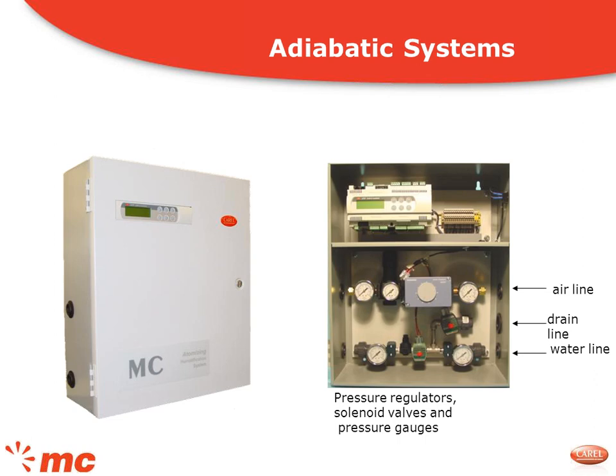Some of the single zone systems that you see are some of the zone controllers that can also be used, like this one that you see here. Just to see inside the box, you've got the direct air line where pressurized air would come in, and then you have your water line. You would supply both the air line and the water line to these distribution tubes where it's combined at that nozzle. But not a lot of components, as you can see: pressure regulators, solenoid valves, and a pressure gauge.